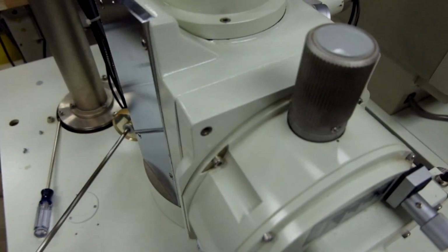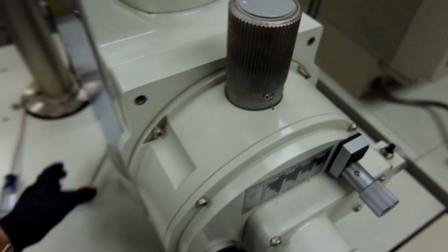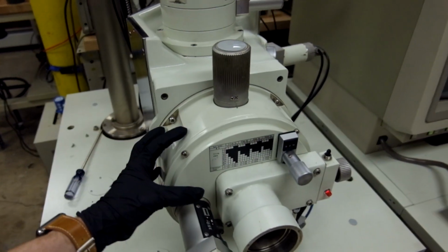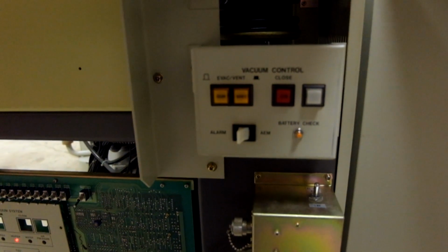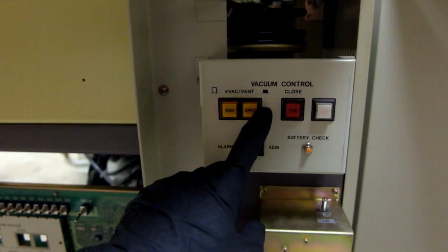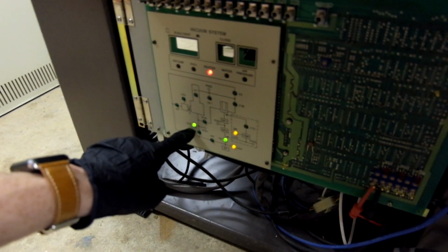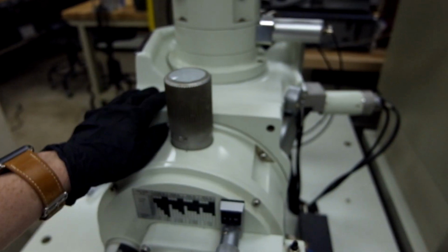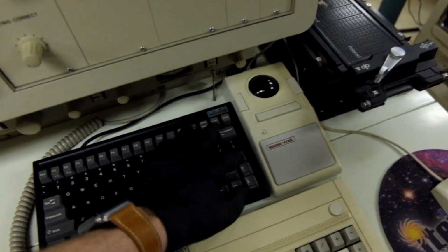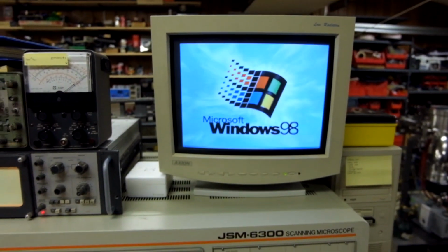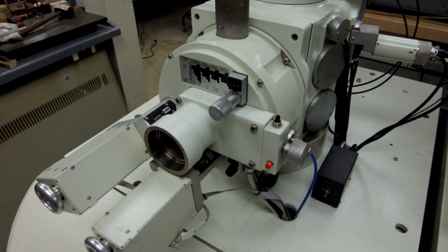But I want to show you the whole inside of this. So I have to bring this up to atmosphere, and then it's going to slide out. So to do that, we go down here on the vacuum control, and we can vent the gun or the specimen chamber. I'm going to vent the specimen chamber. So I'll hit that. Valve LV3 will open. That flows nitrogen into this chamber, and then in a couple minutes I'm going to be able to draw that out. The computer's booting up here. There we go. Alright, this guy's ready to be drawn out.